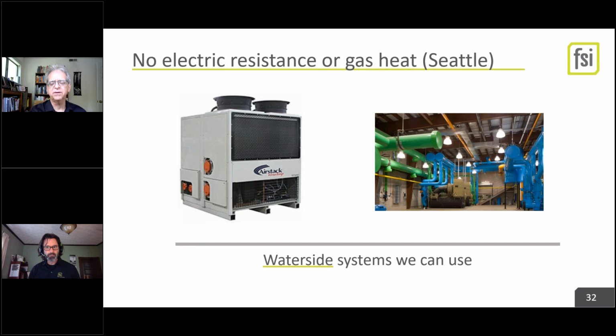Now, wait a second, Ben. I've never understood this nomenclature. This unit on the left is intended for heating, but you're calling it a heat pump chiller, right? Sure. So just like we were saying, if we're going to use heat pumps for heating, you get that benefit of free cooling. Well, a heat pump chiller, you can run it in either direction. It can be heating, and it is much of the year in Seattle, but it will cool just as easily.